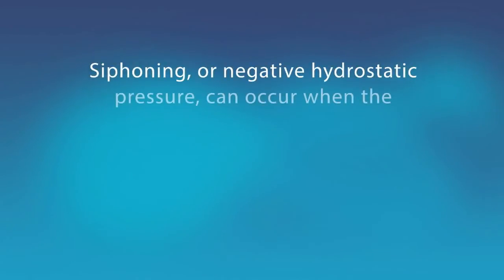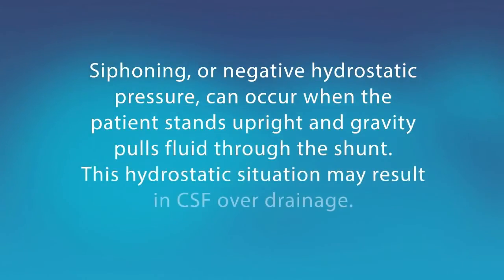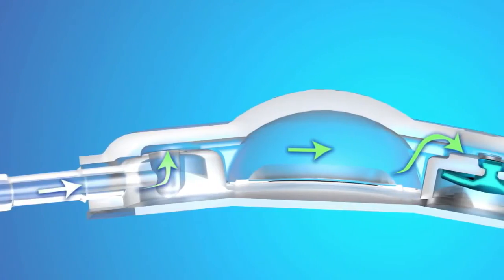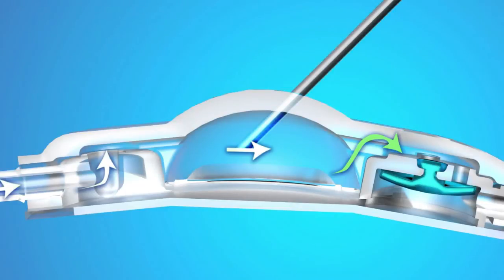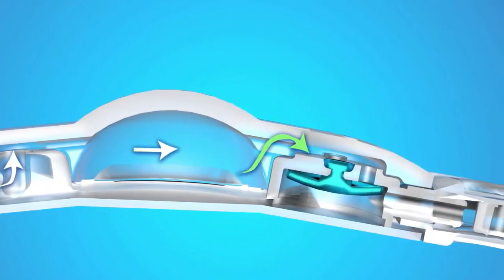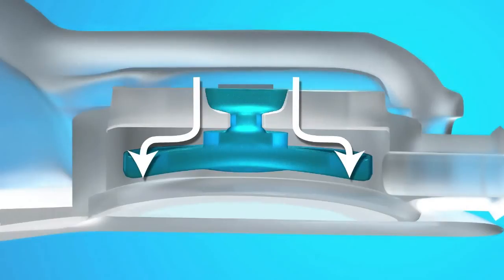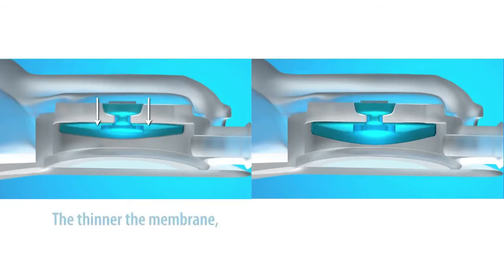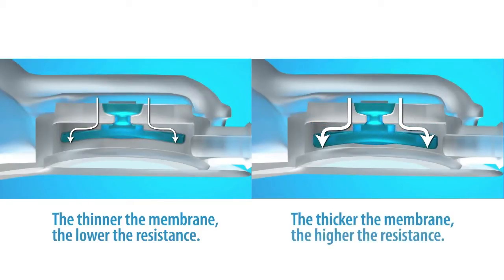Siphoning, or negative hydrostatic pressure, can occur when the patient stands upright and gravity pulls fluid through the shunt. This hydrostatic situation may result in CSF overdrainage. As CSF flows through the Delta Valve, it enters the inlet connector, flows by the proximal occluder, and into the central reservoir. For sampling CSF, the reservoir dome can be accessed using a 25-gauge or smaller non-coring needle. From the reservoir, CSF flows through the valve mechanism flow holes. Like the contoured valve, the Delta Valve also has a silicone membrane valve, or diaphragm, which opens or closes depending on the inlet intracranial pressure. By varying the thickness of the membrane, the amount of pressure needed to open the membrane valve can increase or decrease depending on the valve and pressure level chosen.